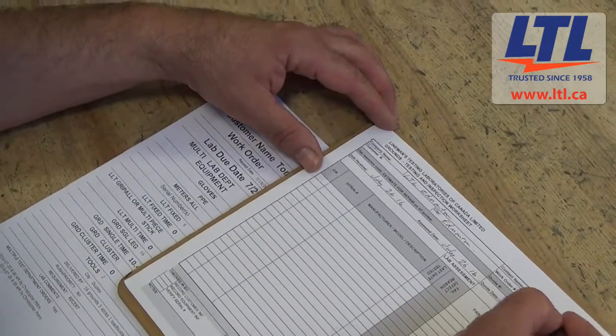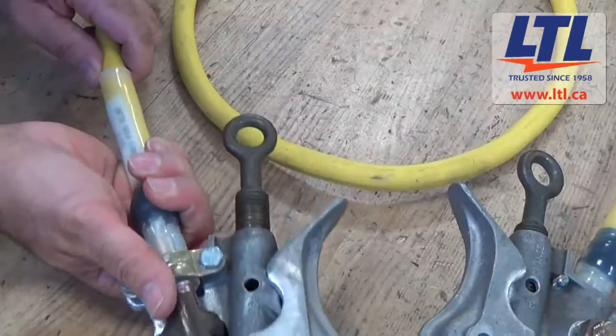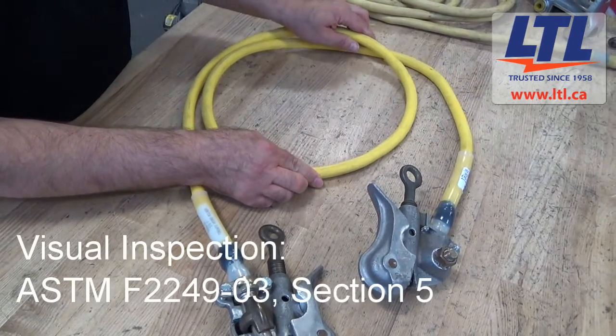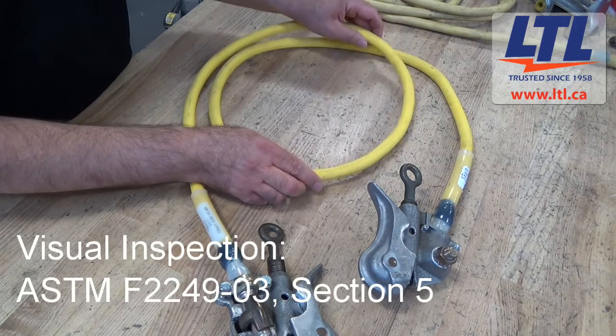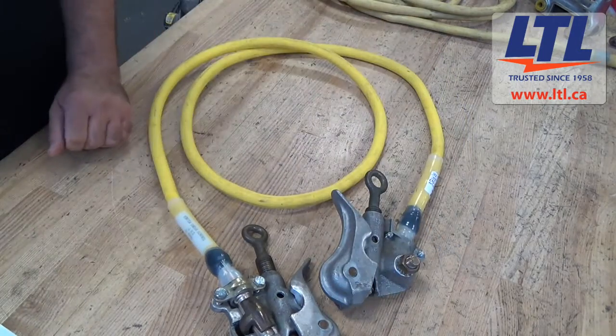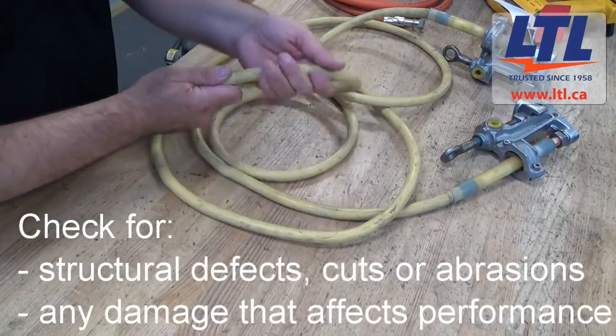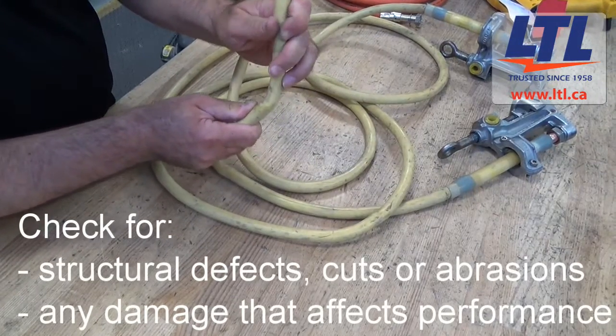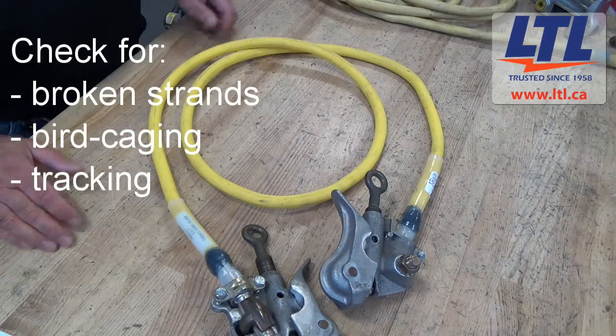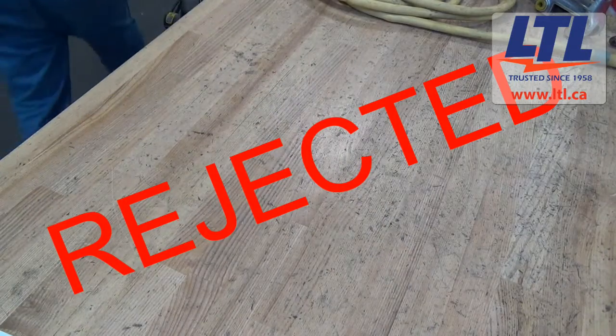When you send your grounding equipment into LTL for service, we first create a customer record for your equipment. We then visually inspect the protective grounding jumper assemblies in accordance to ASTM F2249-03, Section 5. We inspect the cable insulation for structural defects, cuts or abrasions. Any damage detected that may compromise cable performance should be a cause for rejection. We inspect the cable for broken strands and birdcaging, and also look for signs of tracking. If the markings cannot be removed, the jumper cable shall be rejected.